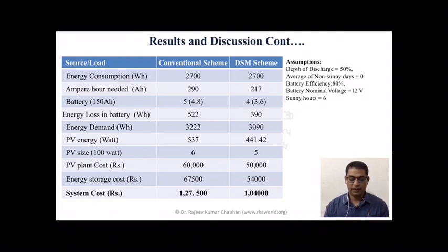So we require 5 batteries with the conventional scheme, while with the demand side management scheme we require 3.6, meaning 4 batteries of 150 Ah. Since we cannot design a battery of 3.6 or 4.8, we have to round up to the higher figure.